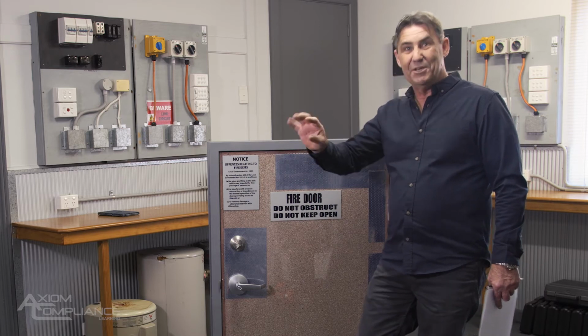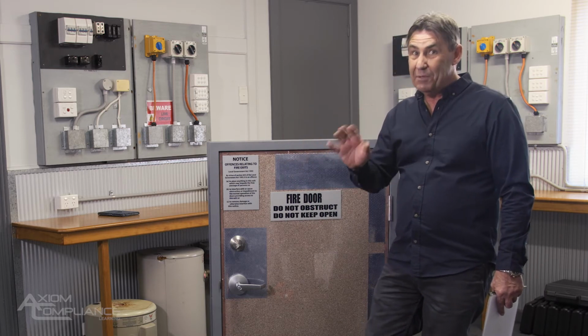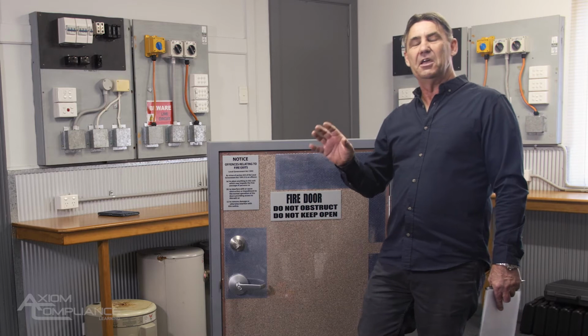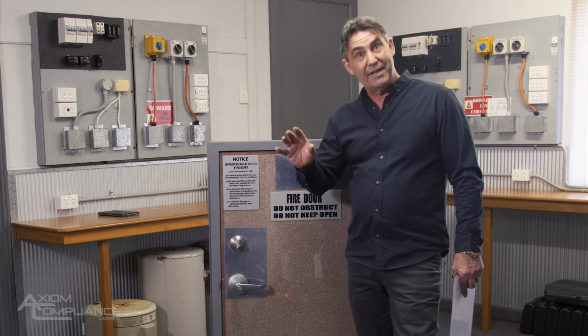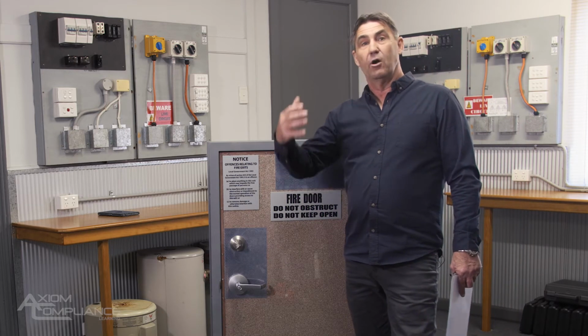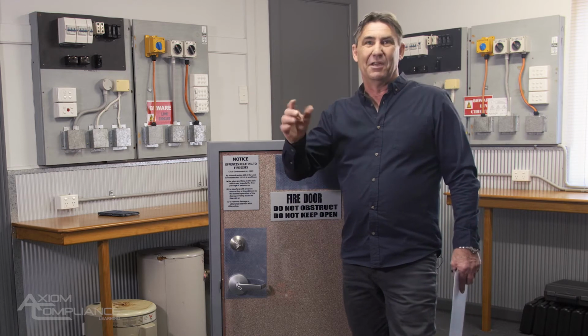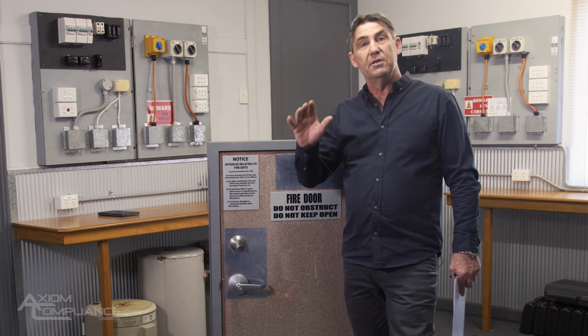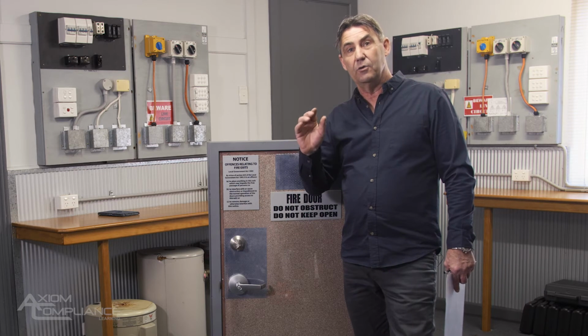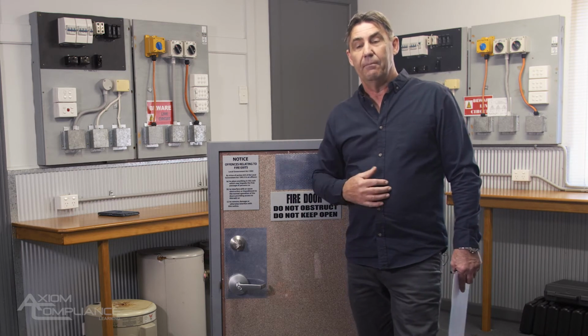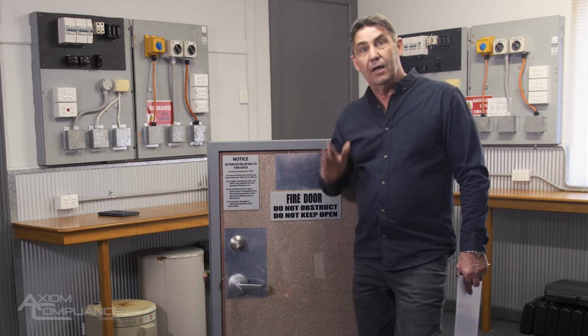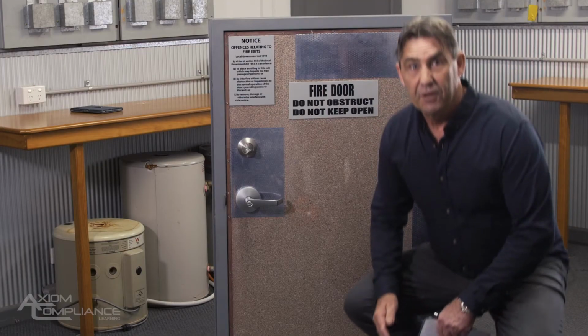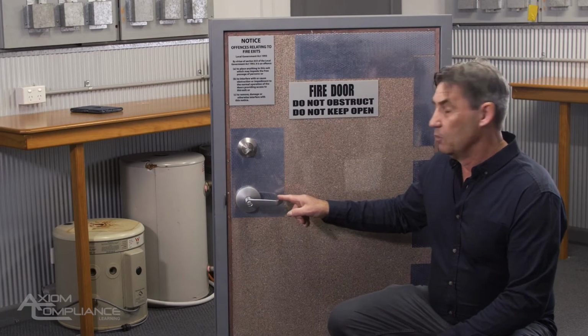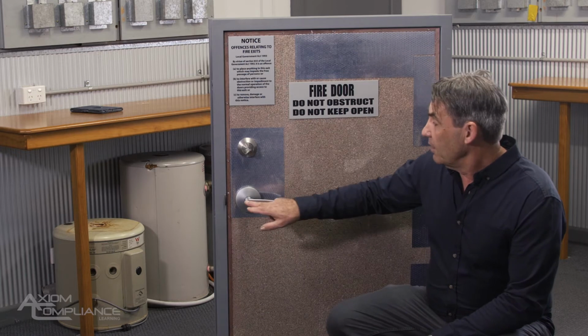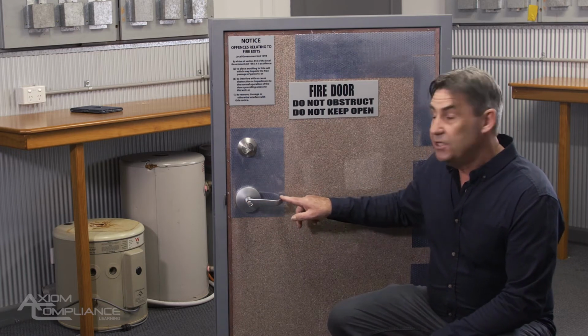So, you know the round knobs you get? Can't be a knob. It can be a knob, okay, if it's on a residential type door. So if you've got a block of units, you can pick your own door setting and use knobs only on a door into a living quarters, okay? All other doors for egress must be what I call a D-shaped handle. So not only is it a lever, but it's a D-shaped handle.